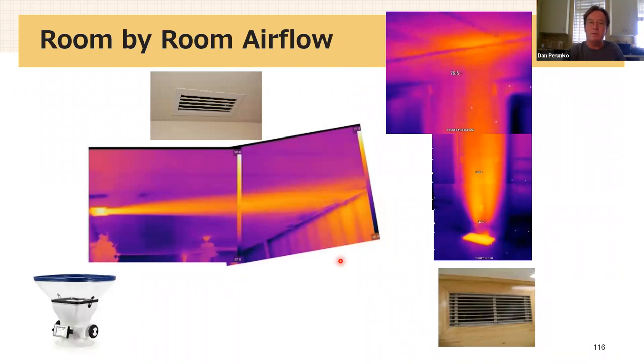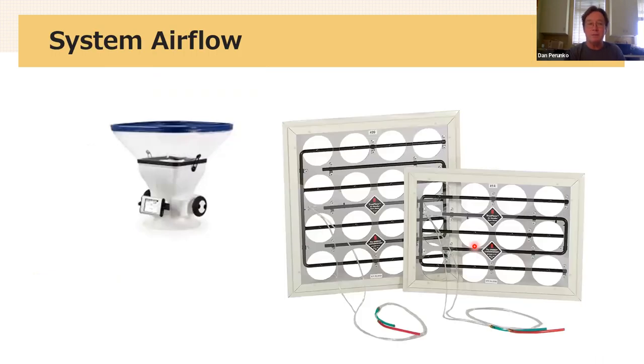Room by room airflow is something that is not in code at all. So we should know how many CFM are delivered to each grill and then build everything to make that happen, including sizing the grill so that we know how far the air goes. And all of that's available information that you can have before install, during install, and then test at commissioning. Total system airflow can be measured as the total of the supplies or as a one unit measurement using a thing called a flow grid.